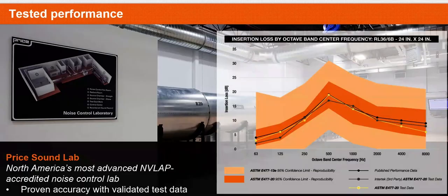Well, you add silencers, and what silencers do is they allow airflow to go through while also offering sound reduction as waves pass through them. Now, the latest standard as it relates to silencers is ASTM E477-20. Yes, you could write that down. That is the most accurate set of performance as you are laying out a specification and you need silencers, whether they are ducted or unducted for outdoor solutions. You want to make sure it's up to the latest standard.